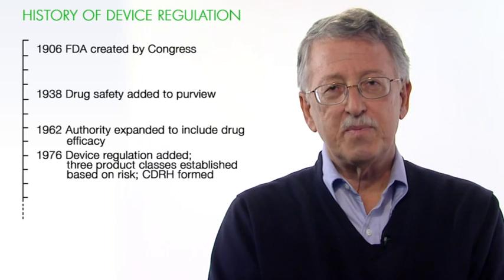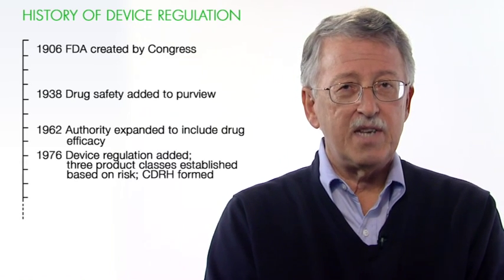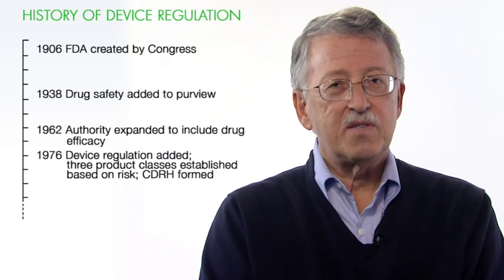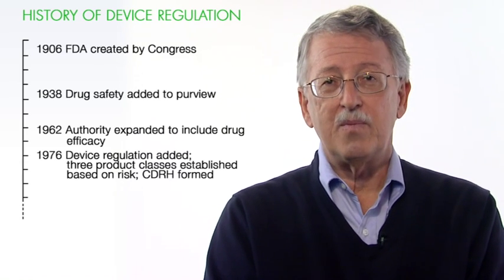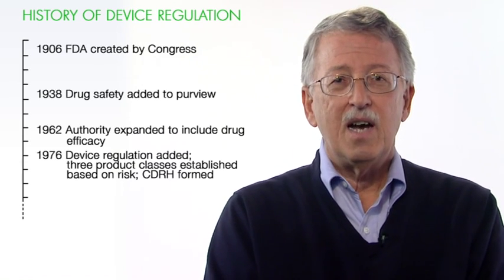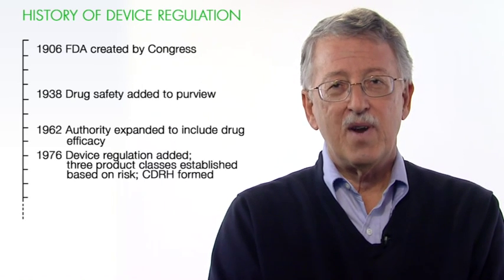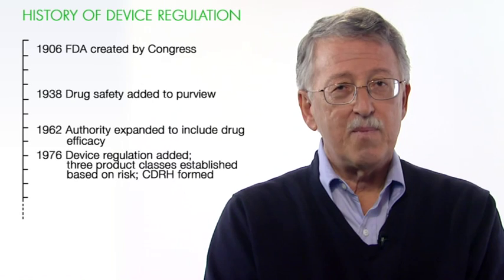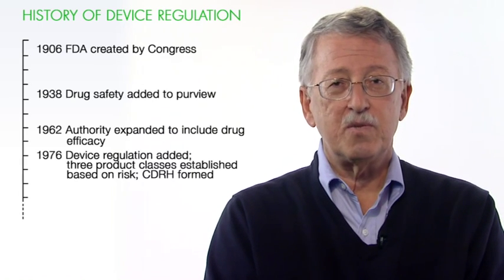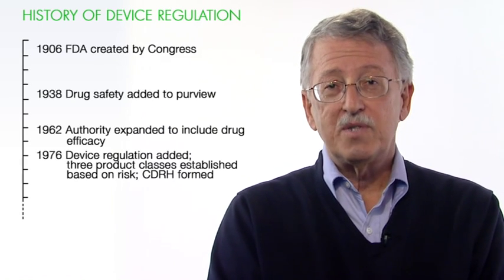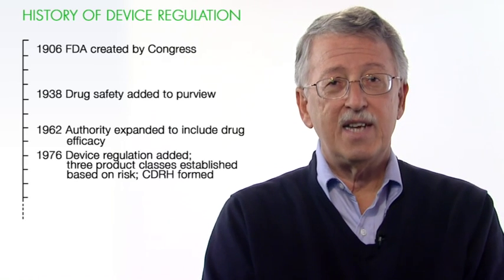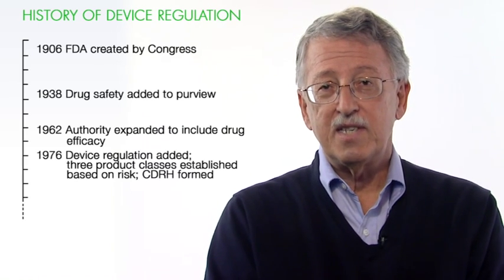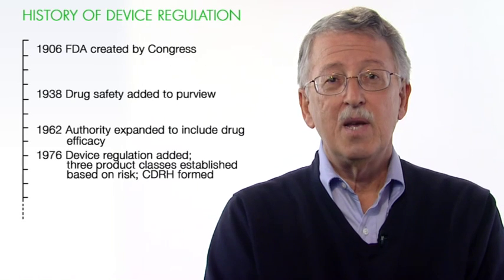The law also contained a number of specific rules with respect to compliance for medical devices. So the challenge was for Congress and for FDA, once the device law was passed, to figure out how to regulate products that could range from things as simple as bandages to very complex products like dialysis machines or pacemakers. When the law was enacted, Congress set up three classes of products according to risk, and additionally they set up three pathways to market based on risk.